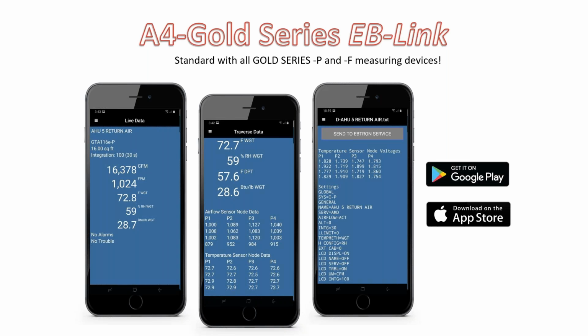Engineers, what I'm seeing some of them do with this device is they're asking the commissioning agent to send them a report once the building's commissioned. And why is that? They want to verify that their system is meeting the design flow requirements on day one. And once you have all this data, again, you can save it directly to your phone. So engineers love that, because if anything ever goes wrong with their system, they can say, hey, day one, this is how it was commissioned. This is what the flow meters were reading on day one when this was commissioned. Contractors really like this because they don't have to get up on a ladder anymore to actually go through the menus of our transmitters. They can connect to this again on their phone, do diagnostics on their phone first.